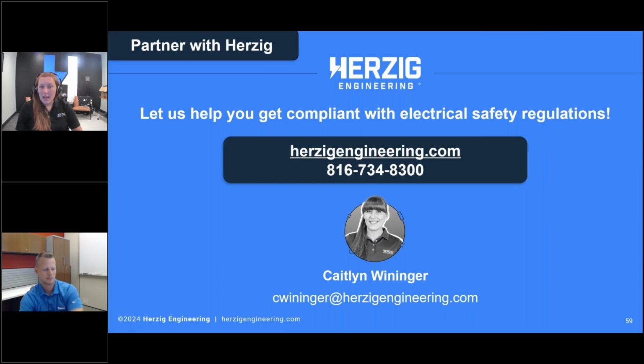So I had somebody ask, what are other electrical safety standards other than 70E that support OSHA? So you had mentioned that it's one of them, and it's honestly the best one. Some others that come to mind are like the IEEE. They have 3007.3, I believe. It's another electrical safety standard. It's not updated nearly frequently enough. I think the latest edition was 2012, if I'm remembering right. There's also the NETA and ANSI and ASTM standards. There's the National Electrical Safety Code. That's more for medium high voltage utility kind of stuff. 70E is really the main one as far as electrical safety.